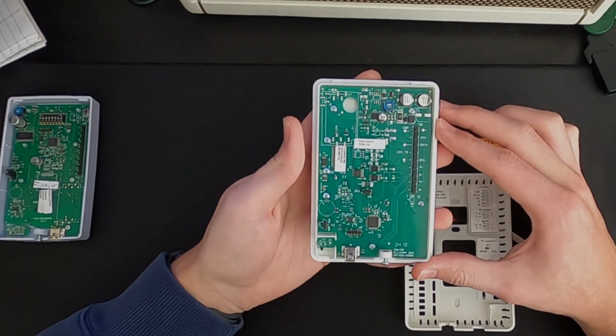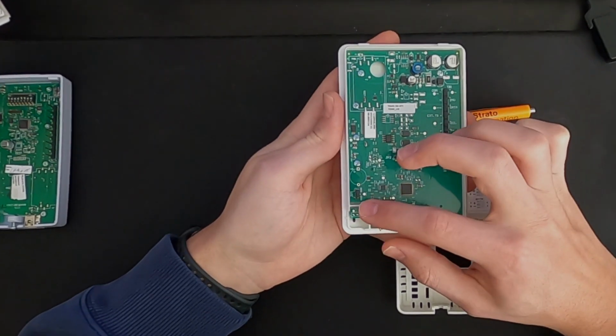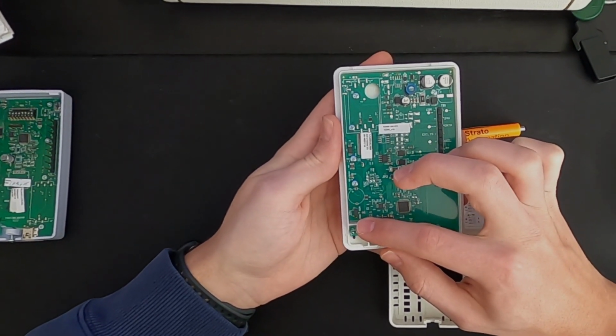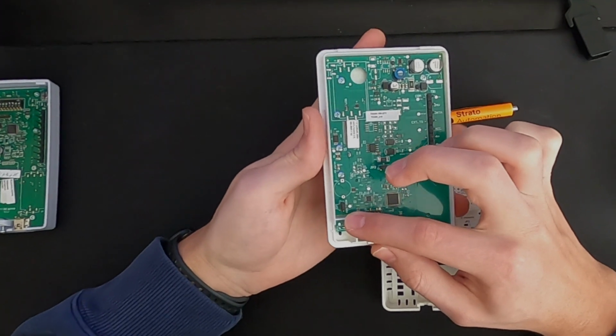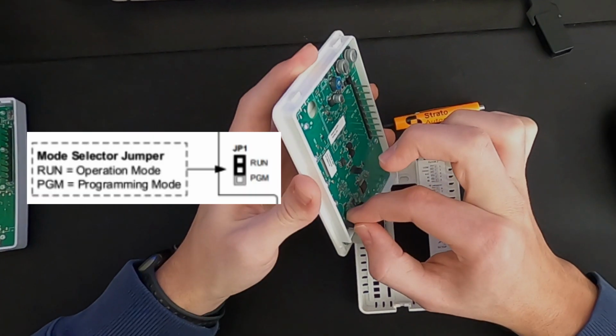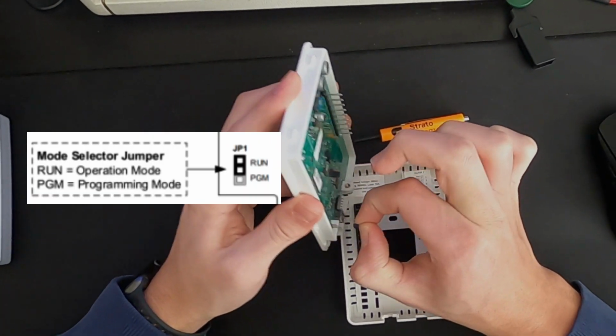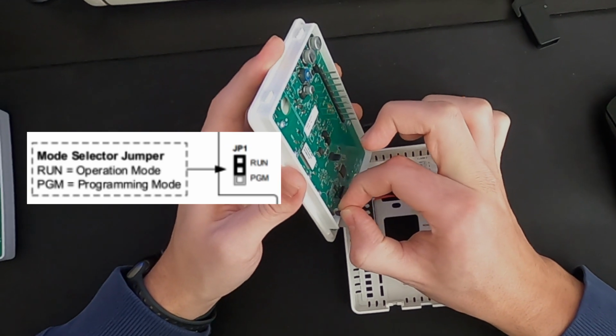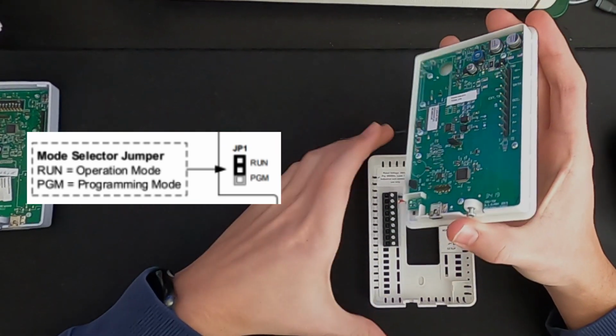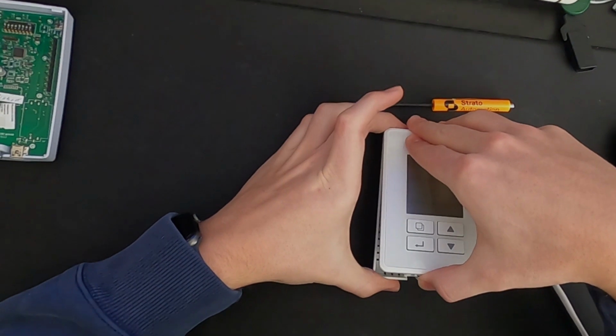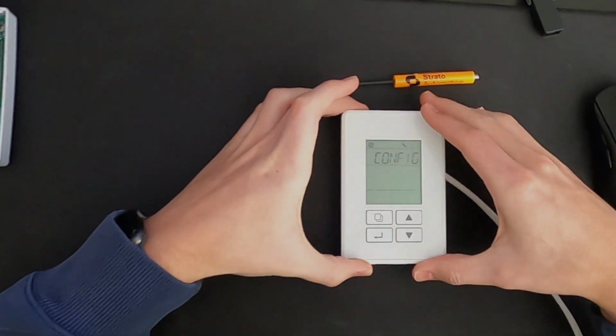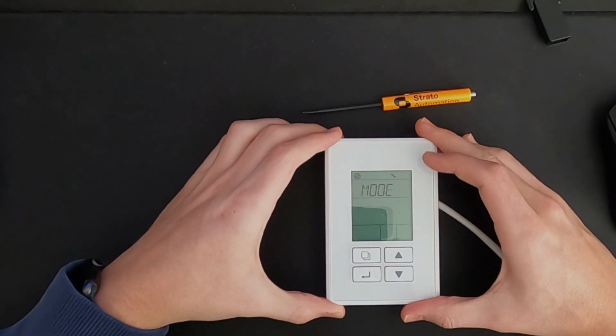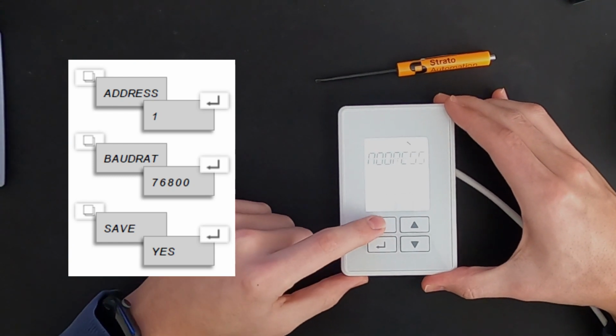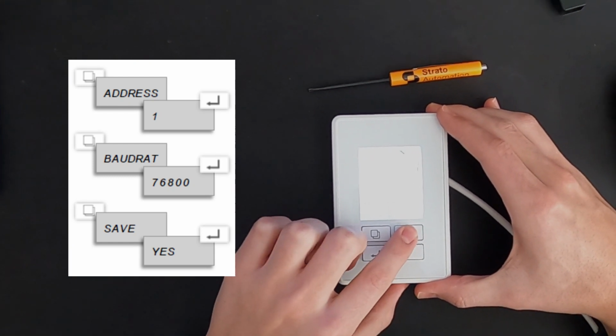To set up the address on the TZ200, down here in the bottom left corner of the PCB, I have JP1, jumper 1. I'm going to move that from the top position, run, to the bottom position, program. I'm going to snap it back into my back plate to give it some power, and it's going to go into configuration mode. I'm going to cycle through and set my address.